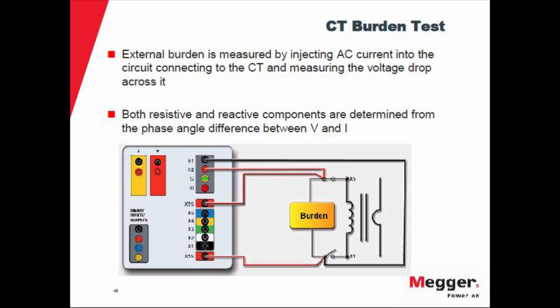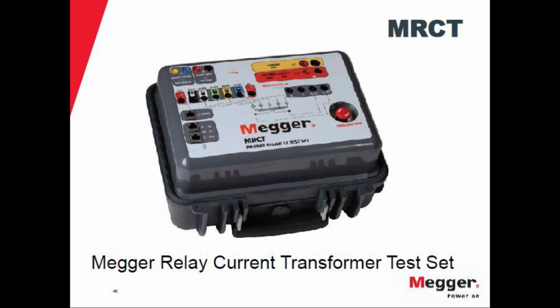And one more test that you perform in CTs is the burden that is connected to the CT. It's actually not a test on the CT, but it is a test to determine what is the resistance of the load that is connected to the CT. CTs have a specification related to the burden that can be connected. If the burden is too high, the CT won't be able to drive current through that resistance, and it will not perform correctly. So the burden connected to the CT has to be measured.